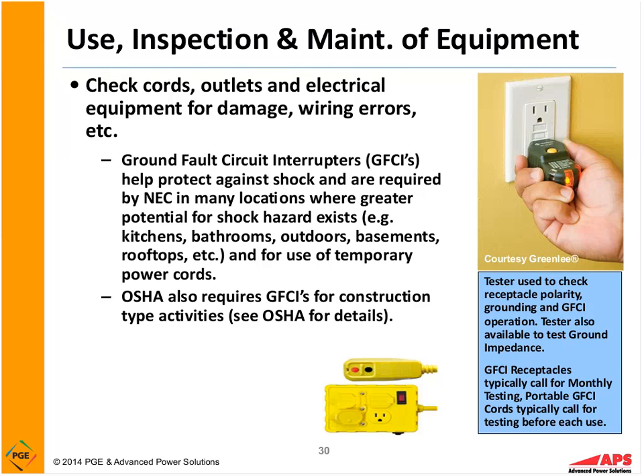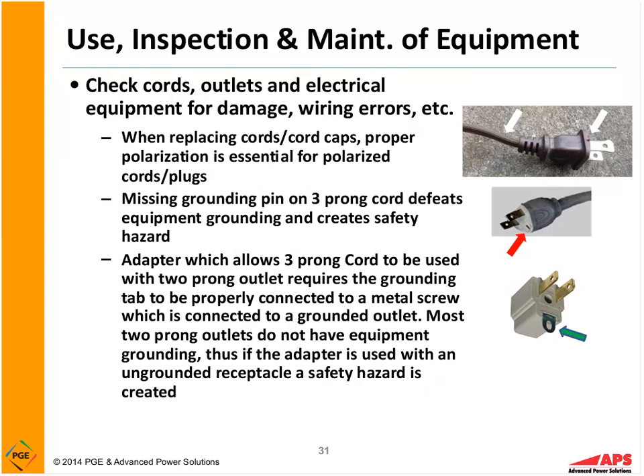In the upper right-hand corner, too, you can see someone using a receptacle tester to verify that the circuit is actually wired properly and that the GFCI is tripping when it's supposed to trip. Very important that we check our receptacles and cords for wiring errors, loose connections, bad grounds, etc. So here, again, is another slide showing the cords and adapters that sometimes get used. In the upper right-hand corner here, we can see that there's a 2-wire extension cord, no ground wire. So in a nutshell, there's no ground in this cord.